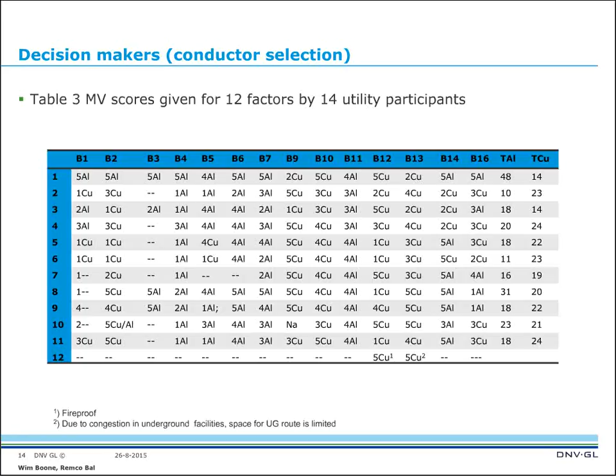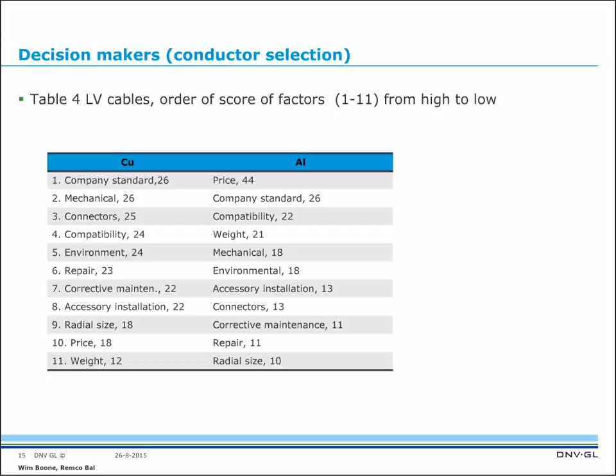And it's clear that for aluminum, the price is number 1, with a very high score, 44. The next one, the company standard, is also high. When you go to copper, company standard is high, and mechanical properties are scoring high. If you go to the bottom, the weight is scoring, of course, low, and the radial size for aluminum is scoring low. What can be expected? Here the medium voltage cables have a similar order of values. High is price, company standards, and mechanical connectors come into the picture. For copper, the expected problems with connectors are much more under control than for aluminum.